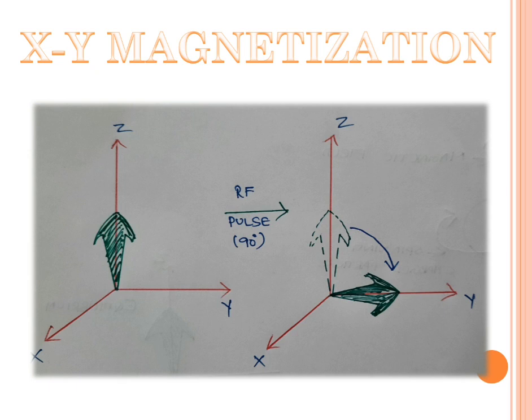If you disturb the equilibrium condition, in the first image you can see that the net magnetization is along the Z axis with no X or Y component — the equilibrium condition. Now if you apply a 90-degree RF pulse, the magnetization that was along the Z axis shifts towards the Y axis or the XY plane. When the magnetization moves towards the XY plane we call it XY magnetization or transverse magnetization, while magnetization along the Z axis is called Z magnetization or longitudinal magnetization.